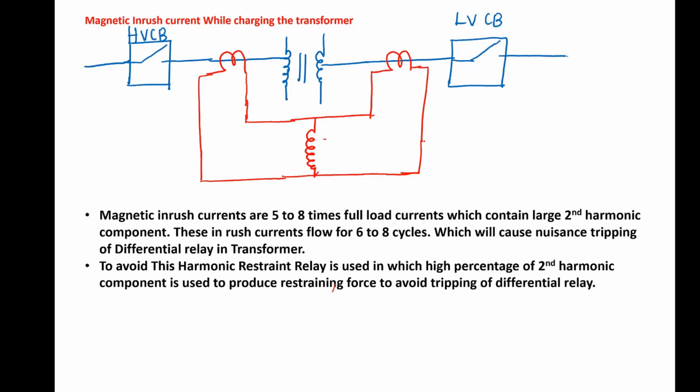Now, suppose the transformer is under no load condition or some breakdown happened, which we have repaired, and now we are charging the transformer for the first time. How do you charge the transformer? You will close the breaker on the high voltage side, that is source side, but the load side breaker will be in the open condition.